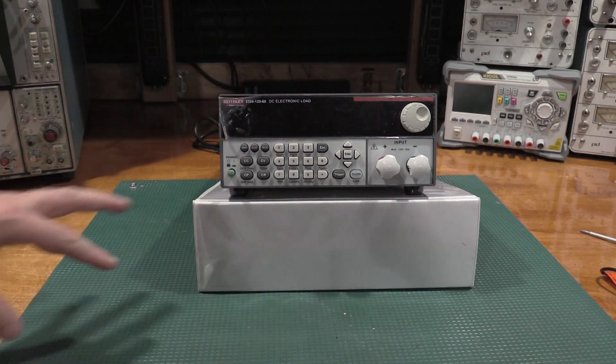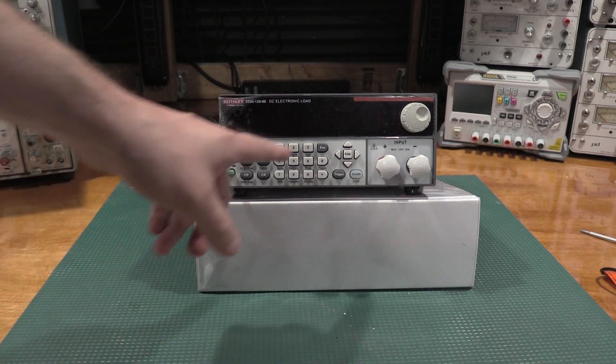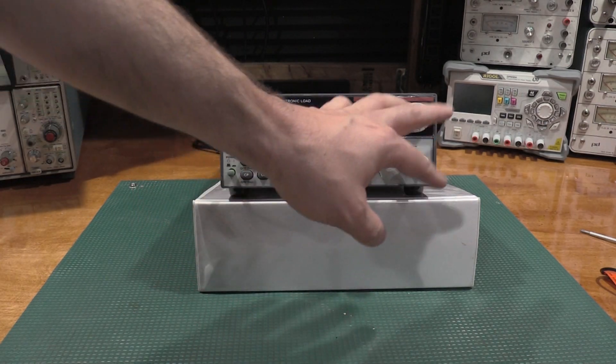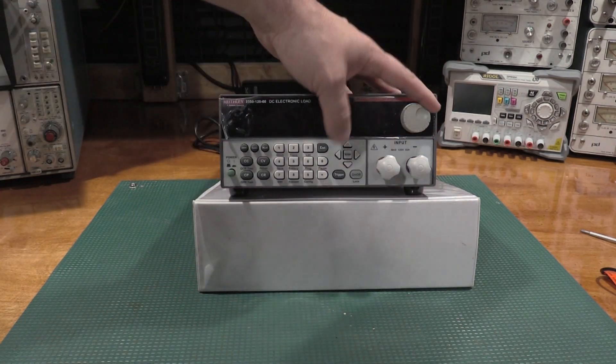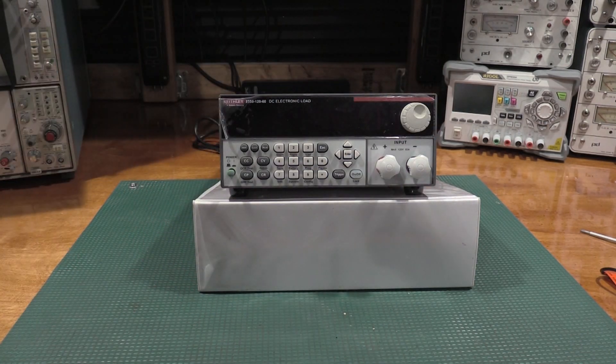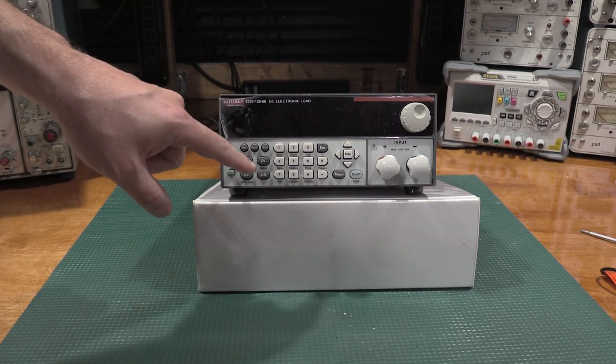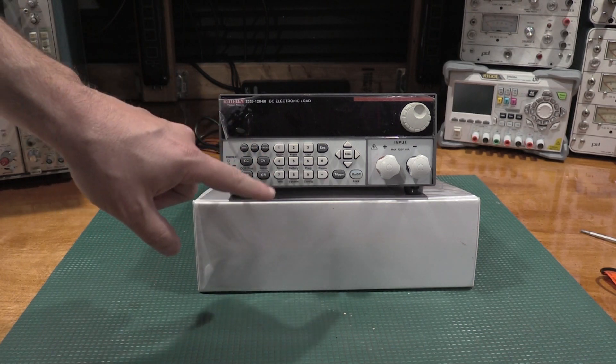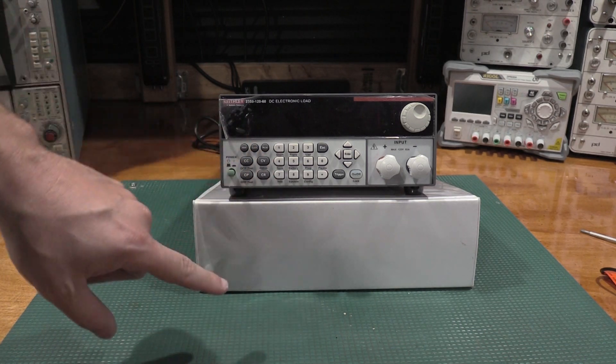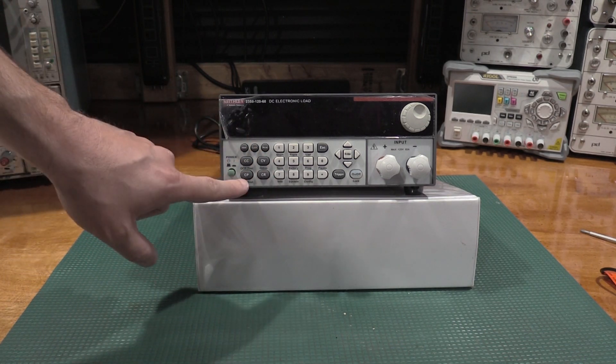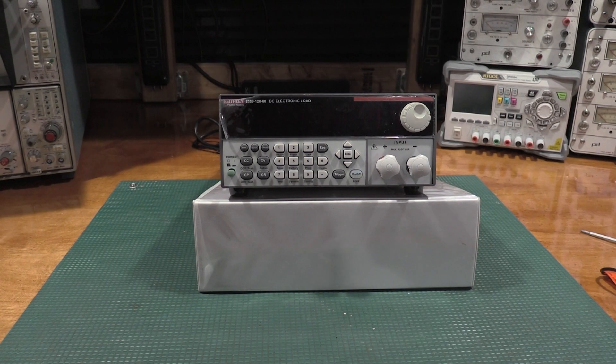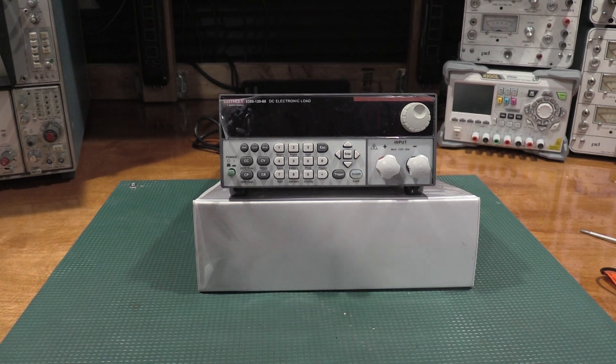It can do 60 amps of current or 120 volts, depending on, as long as we don't go over 250 watts. So, this little guy can dissipate 250 watts, which is actually kind of impressive for its size. Front panel's pretty simple. Keypad, big binding posts, small knob. We have constant current, constant voltage, constant resistance, and constant power tests that we can run on devices.